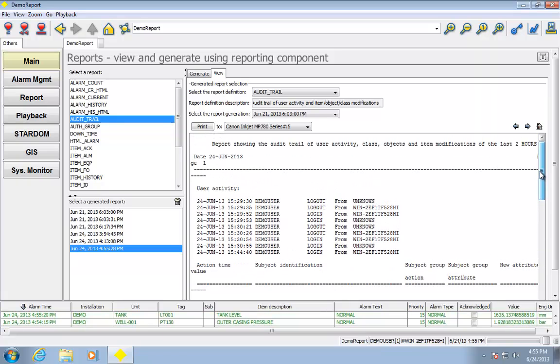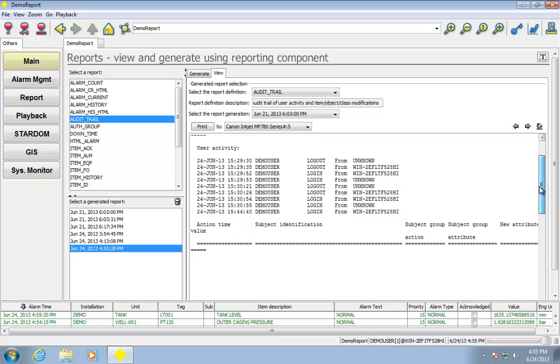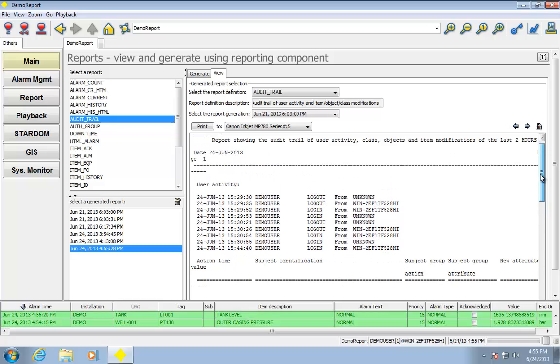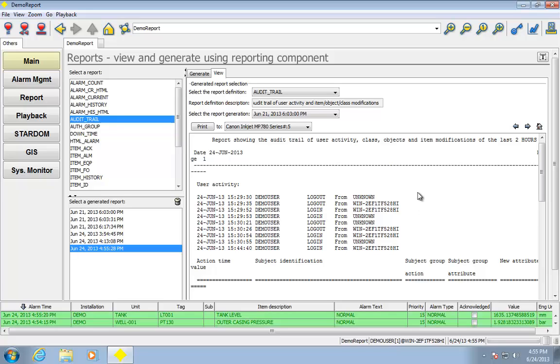Those are all the people that logged in and logged out. I wasn't editing the system. If I had gone ahead and edited the system, all the edits and changes are there. So if you're in the pharmaceutical area, we've got full support for 21 CFR Part 11 audit trail type requirements.